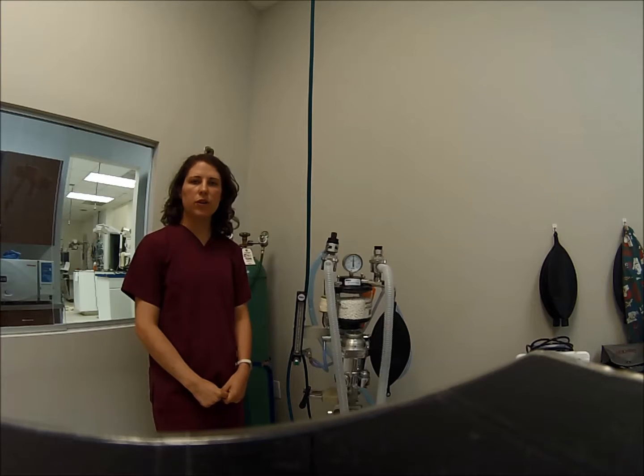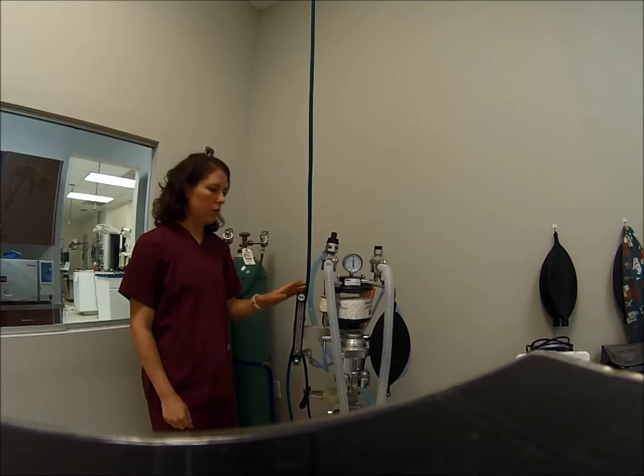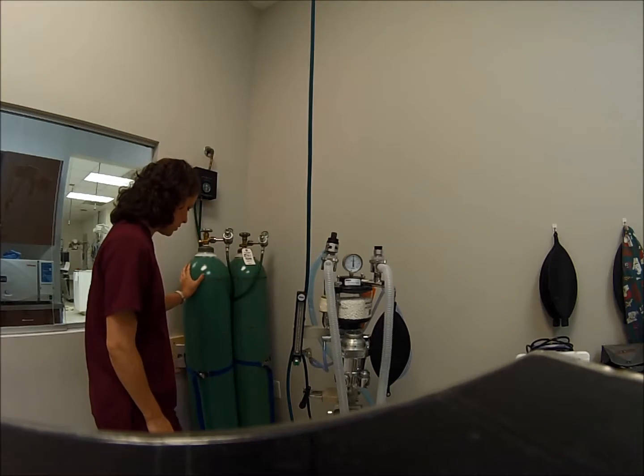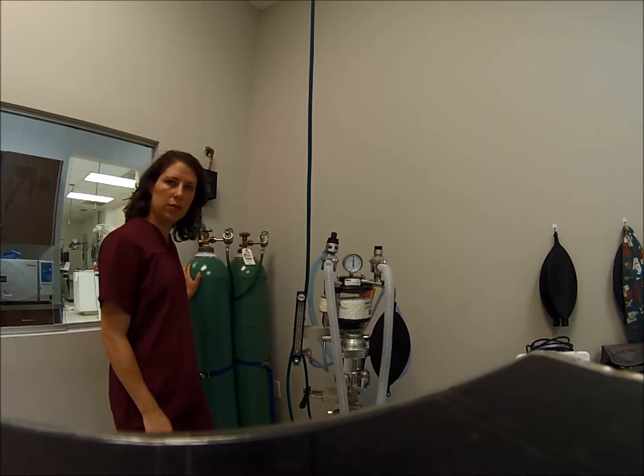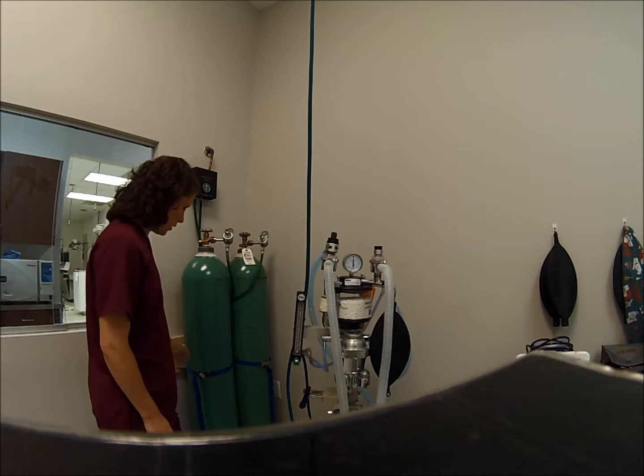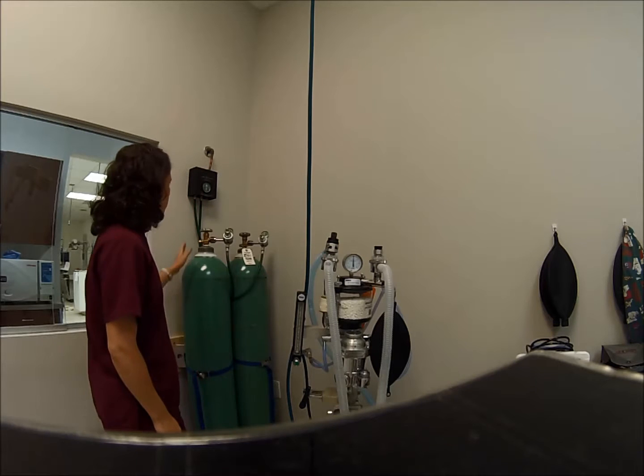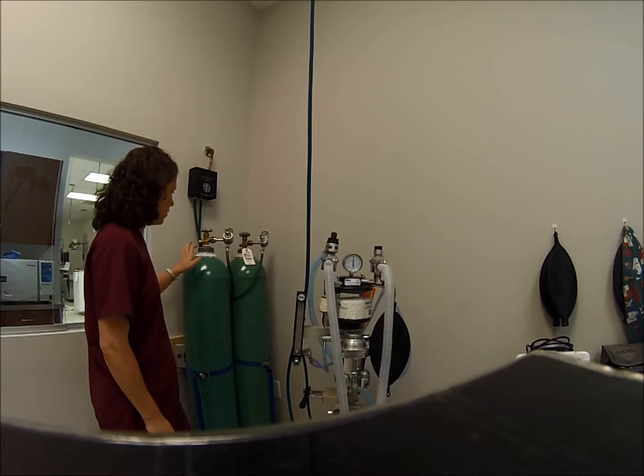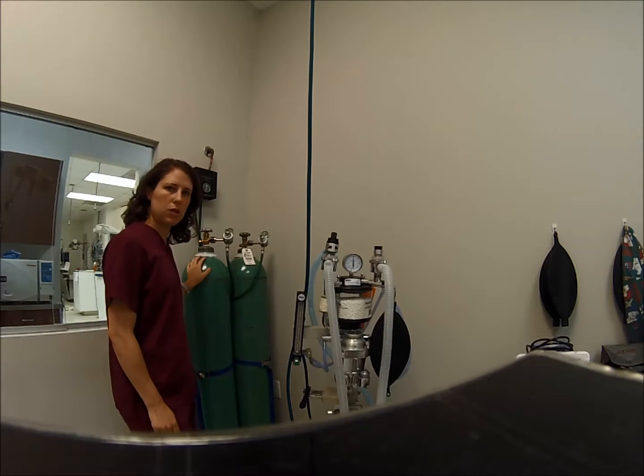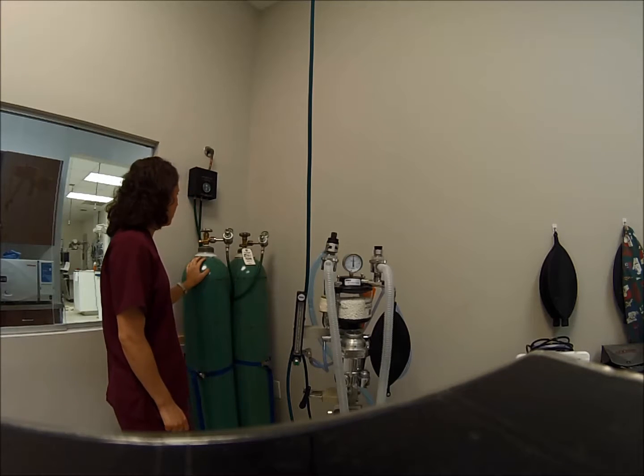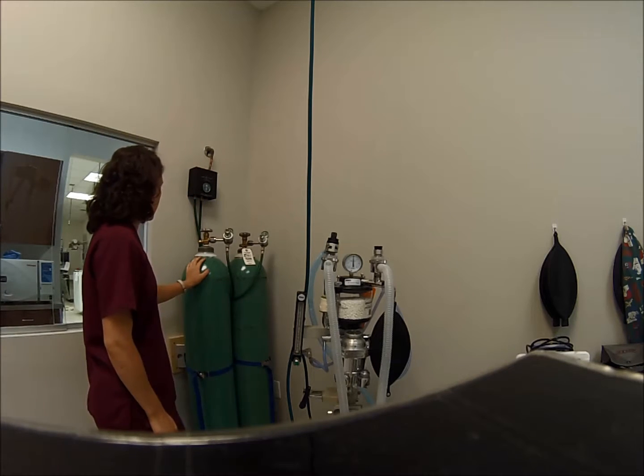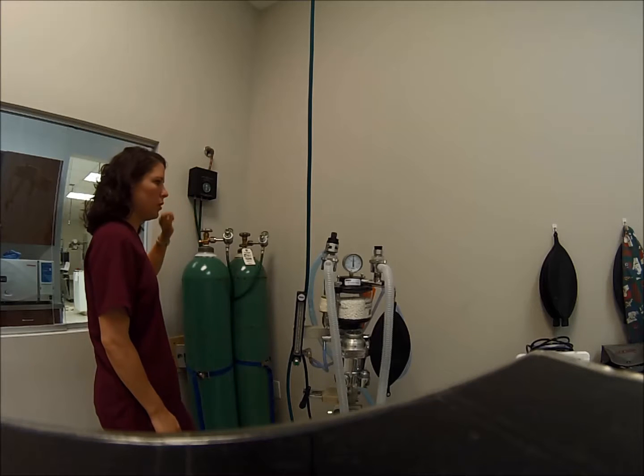Demonstrating the parts and functions of the anesthesia machine. First, we have our oxygen tanks. These are the larger H tanks that are secured to the wall and strapped. The pressure reducing valve takes the pressure from the tank and reduces it to 45 psi, and then the oxygen travels to the lines.